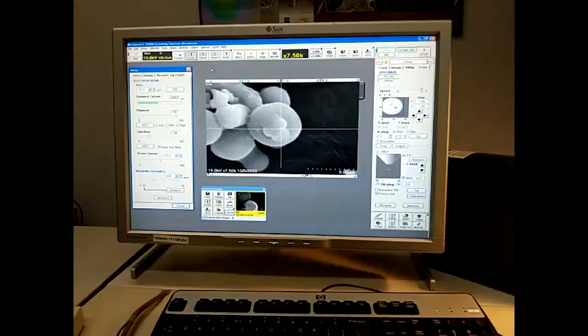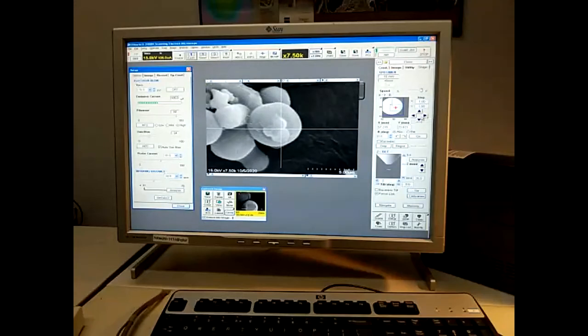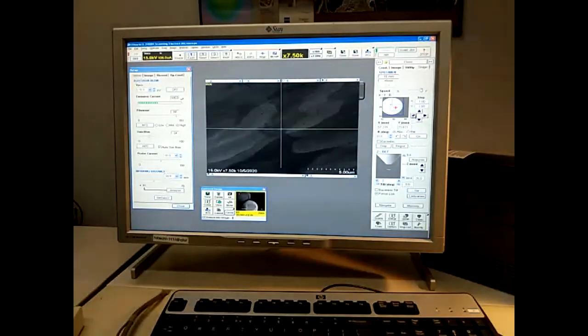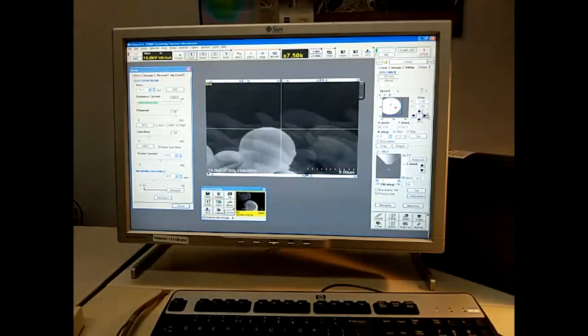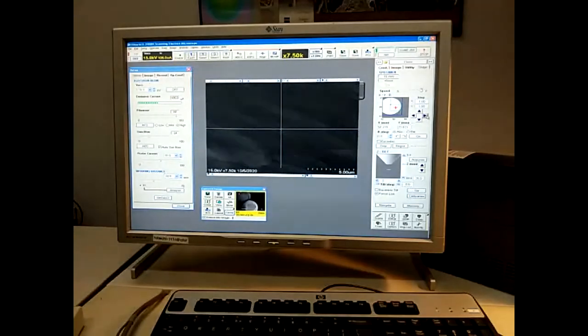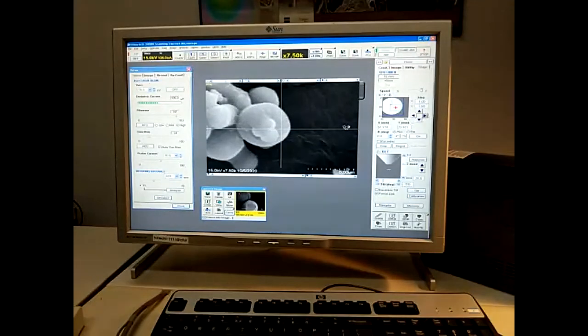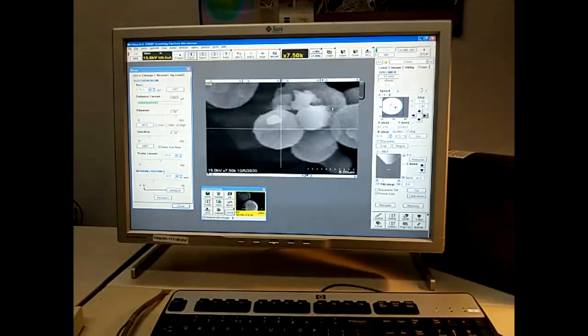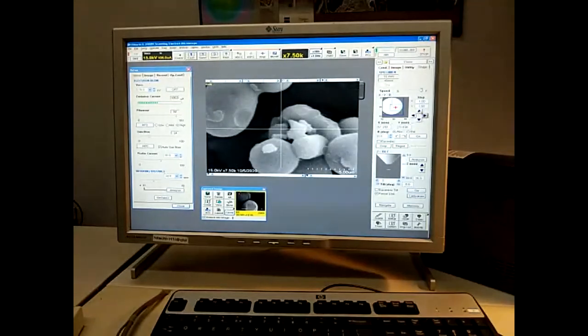I'm back to 15 kilovolts right now. Just wanted to show you a bit of the stage operations. The stage is capable of moving in any increment that you like to enter. We can have an auto move back and forth to two different locations. Should land exactly where we started from. We have a track ball on the table that we can use for stage motion, so I'll just demonstrate that.